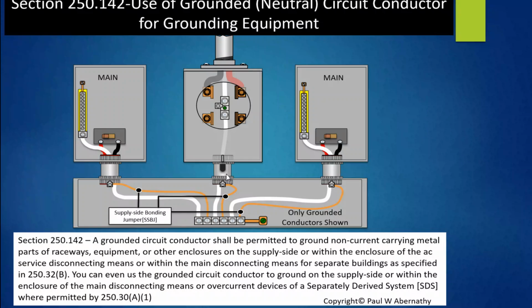Now you get down to this raceway. Let's assume now that these have concentric or eccentric knockouts. Either they're center ringed or they're eccentric out from the center. And I've knocked a few of them out, but I haven't knocked them all out. Well, because that is considered an impaired entry, we're going to have to use a bonding bushing with a bonding jumper. And here's my bonding jumper. I size this supply side bonding jumper based on the size of the conductors serving here.